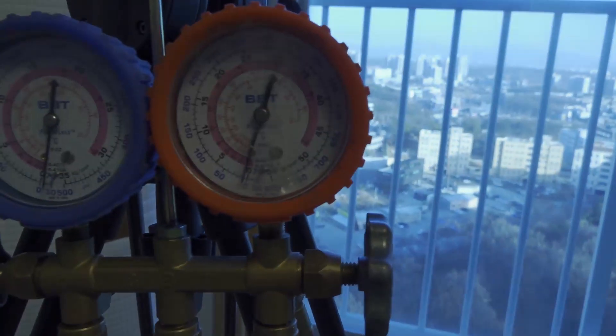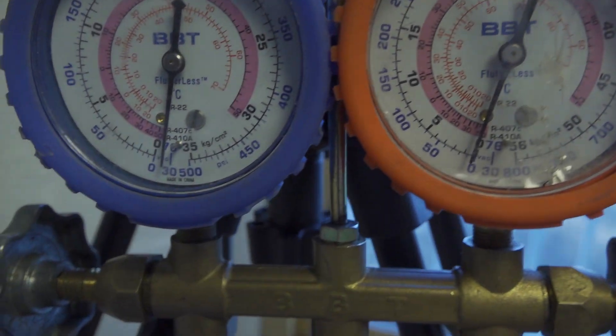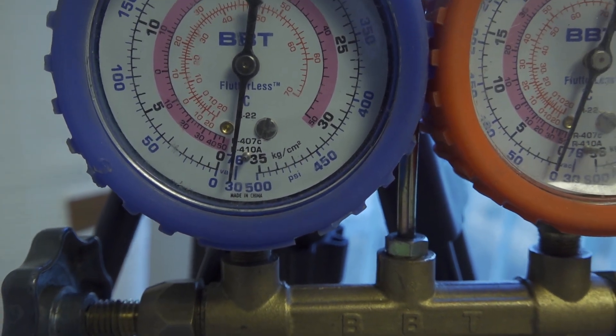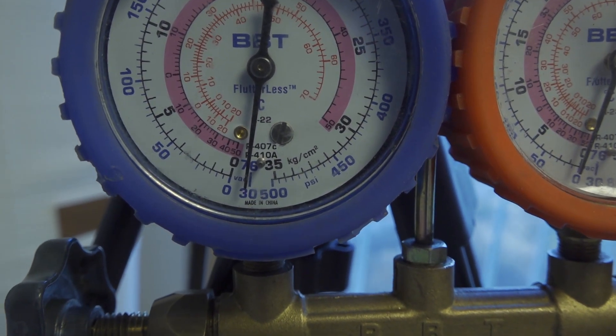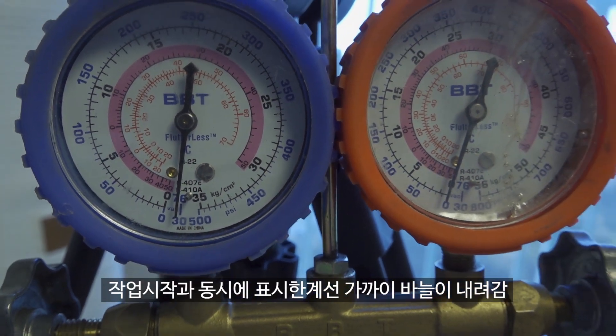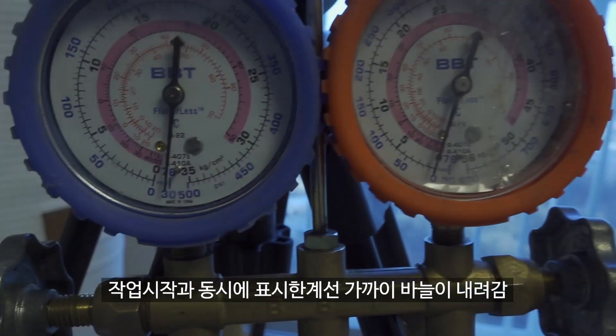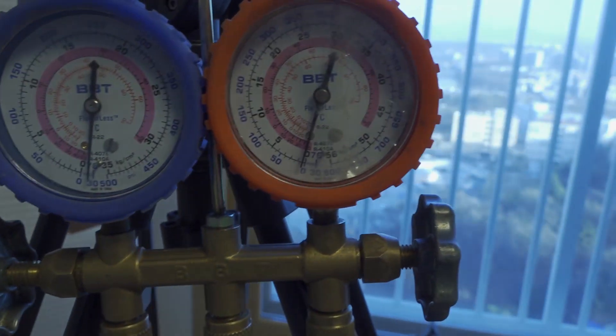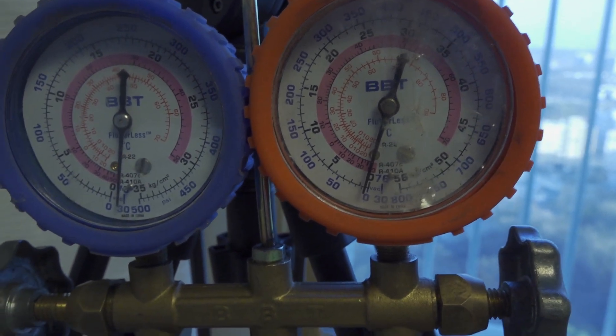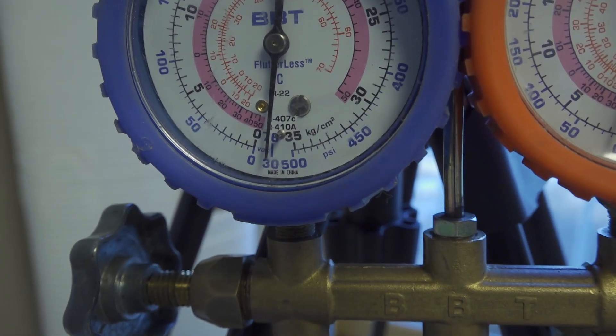As soon as I start the machine, the needle goes down close to minus 30. Actually, you can barely see the vacuum level on the manifold gauge because it drops immediately when you turn it on.